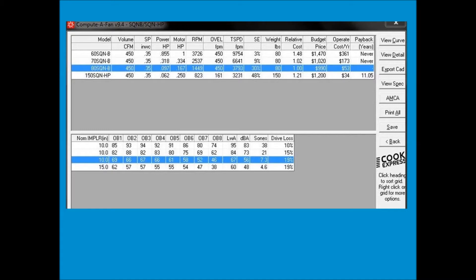The sound level is 83 decibels, which is very, very loud. The next size fan, a size 70, that's down to 2,500 RPM, which is still awfully fast for a small fan. The sound's gone down somewhat, but it's still loud. The selection highlighted in blue, size 80 — now we're down to less than 1,500 RPM.